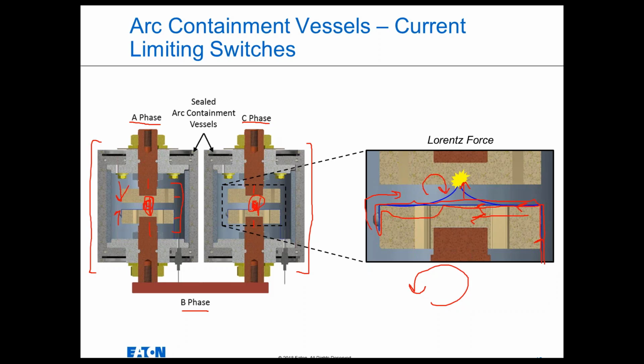It reignites as an arcing fault fully contained inside these arc containment vessels. There's no venting outside these arc containment vessels. That energy is fully contained. But since we used an arcing fault instead of a bolted fault to create this path of lower impedance, we've introduced some impedance so that it draws less peak fault current.